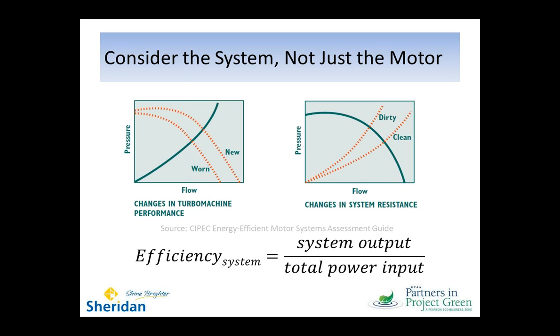And you can't discount the effects of things like belt slippage, making sure that things are at correct tightness, using notched belts and synchronous belts instead of V-belts. Things like that can help keep us on that optimum point for a longer period of time. And I've included here also just a quick calculation that you can use to keep track of whether there's been changes in your system, or whether a change you've made has had a good effect or a detrimental effect. The idea is really quite simple.